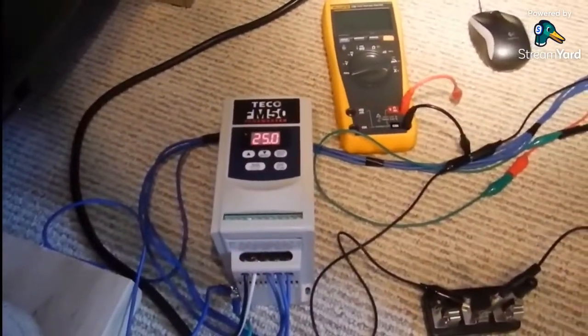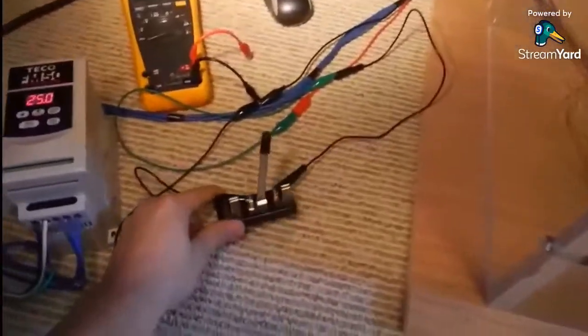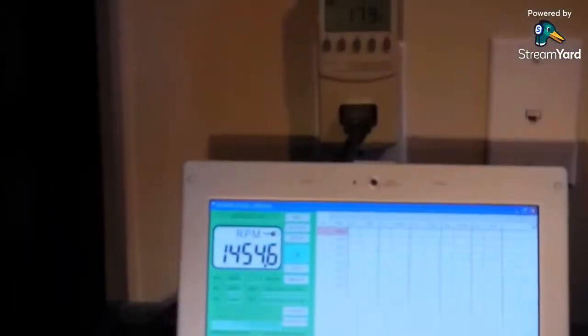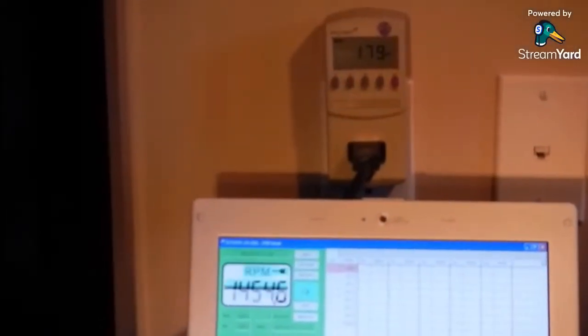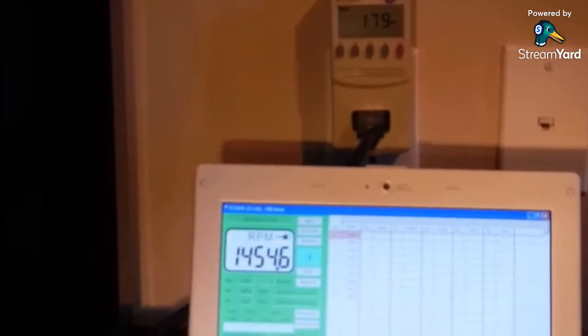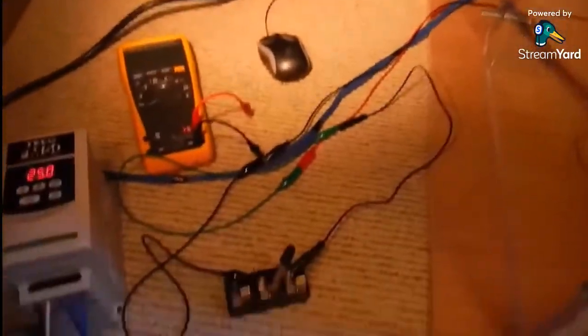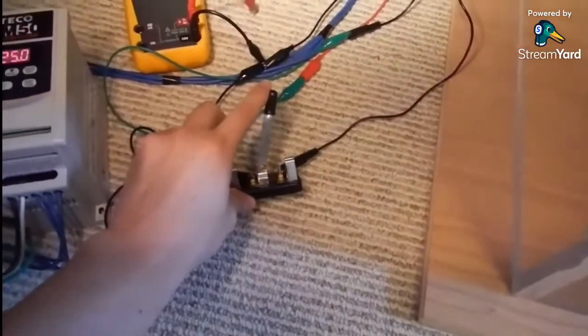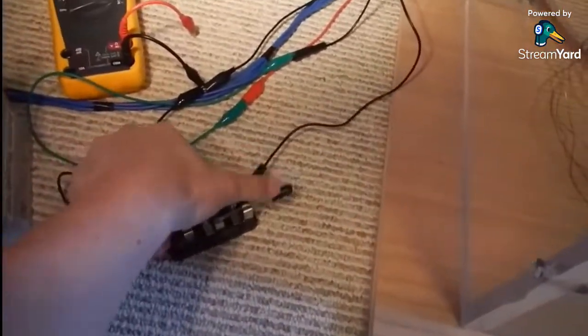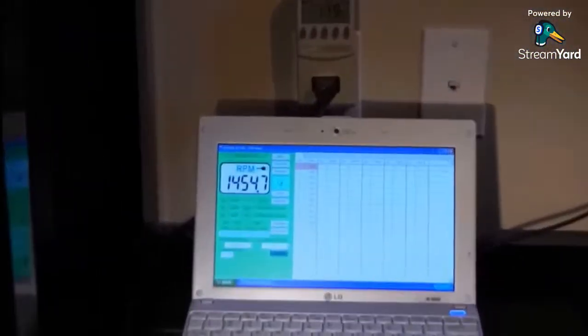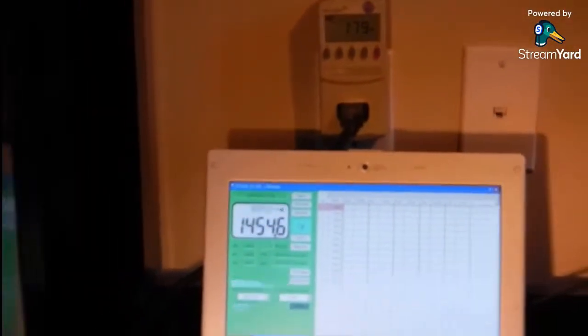Okay, so the disc is spinning now at 25 hertz input frequency, and the switch is open, and my speed is about 1454 RPM, and my input watts is about 179 watts. So now if I take this coil and short it... you can see the input wattage really hasn't changed, and the speed really hasn't changed either.